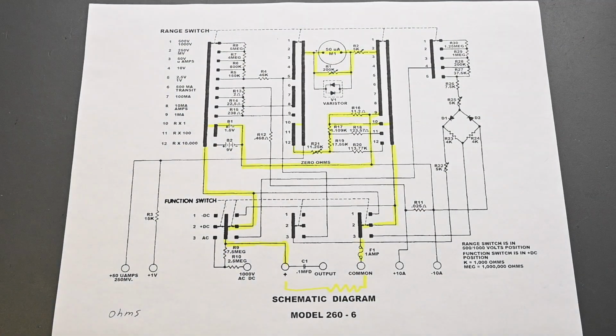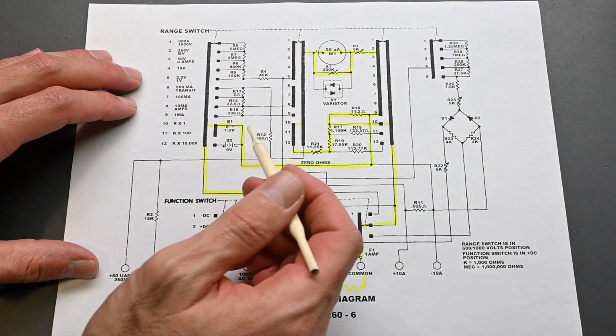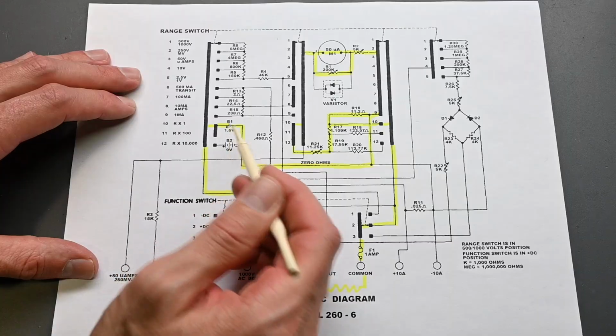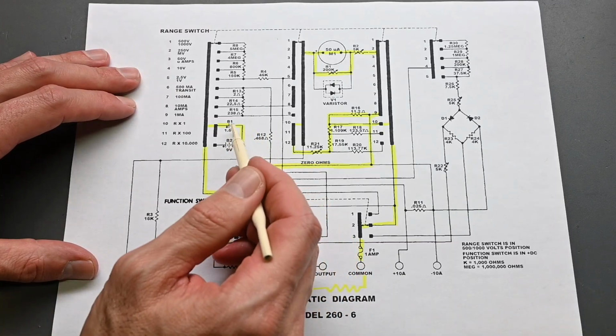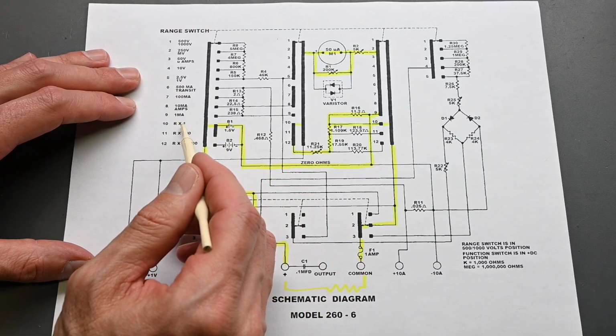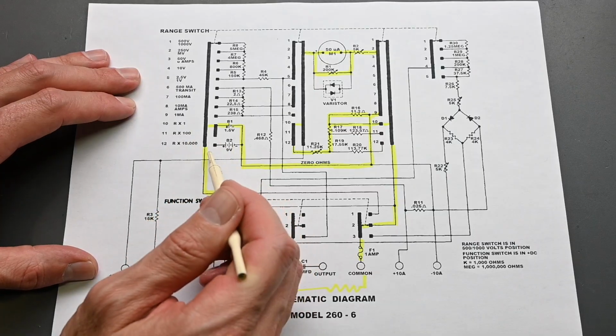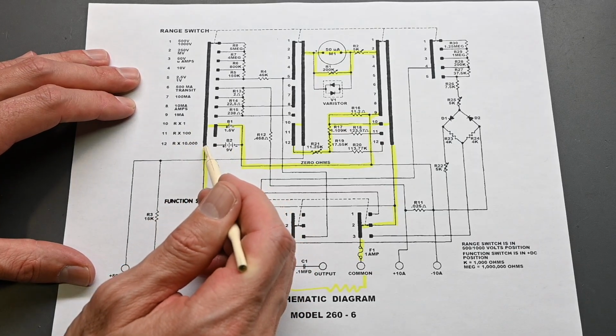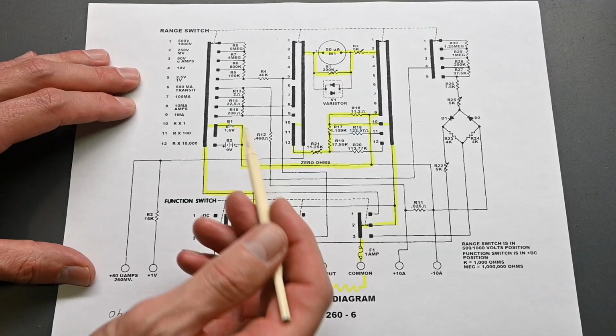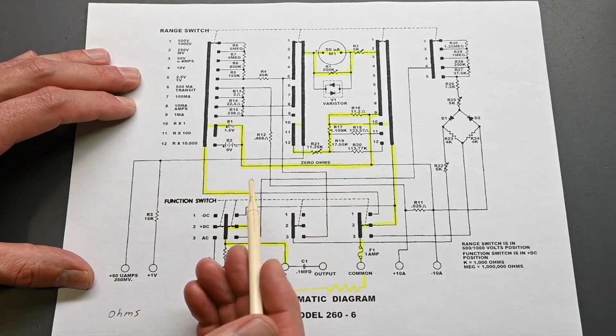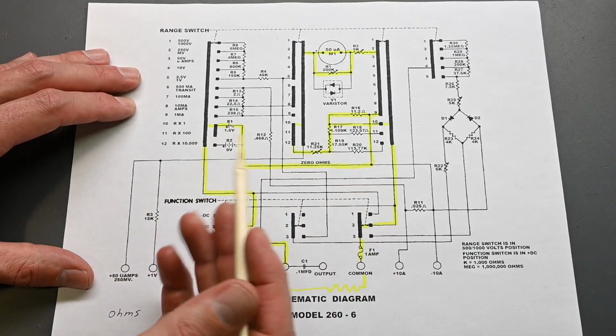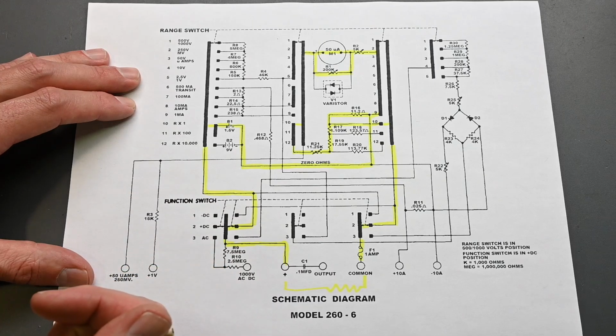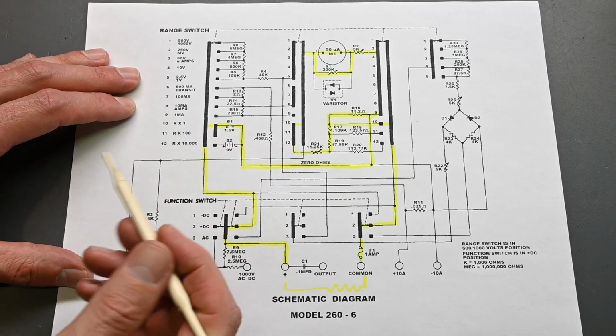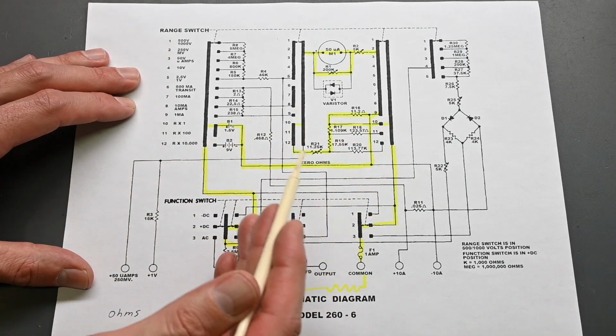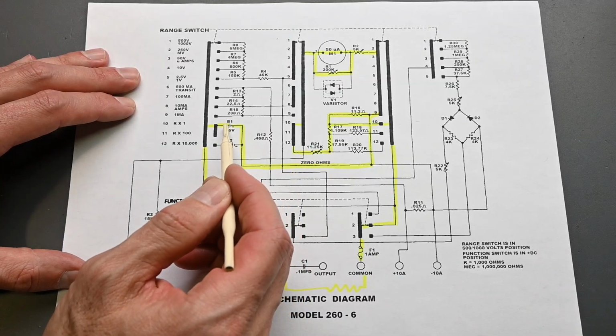Now let's look at the ohms or resistance measurement function. In the schematic there's a 1.5 volt D-cell battery and a 9 volt battery. The 1.5 volt battery is used only on the R times 1 and R times 100 settings, while the 9 volt is used on the R times 10,000 setting. The batteries are only used in this ohms function - everything else about the meter is a passive design that doesn't require any power. It's easier to understand the resistance measurement function if you start with the battery and work from there.